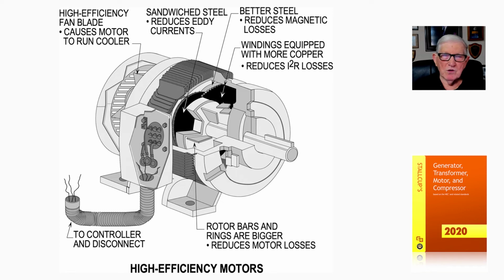So remember, a circuit breaker, 600 volts or less, basically will pull 3 times its rating. So if you had a 100 amp circuit breaker, 300 amps. If you had a fuse, now, they'll pull about 5 times their rating. So that'd be 5 times 100, 500 amps. So you can see it's very important: what is your existing system? If it's an instantaneous trip circuit breaker, how high will the instantaneous trip be allowed to set? And can you set it above the inrush starting current of this high efficiency motor, which would be very high?